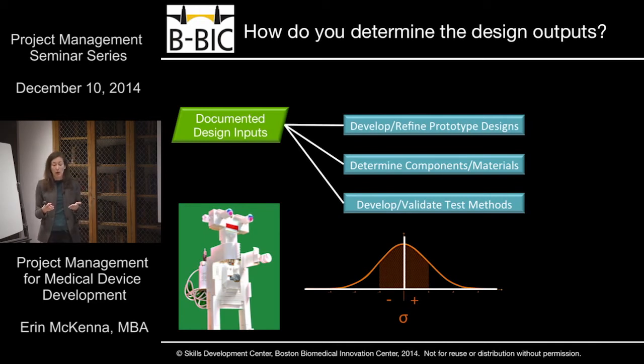You're going to also want to know, does my product need to be sterilized? If it needs to undergo some kind of an end sterilization, what is that sterilization and what effect might it have on my materials? So you're choosing things that would survive a radiation sterilization if you need to plan for a radiation sterilization. The other thing that you do need to do here and think about are the test methods that you're going to use to measure all of these things.